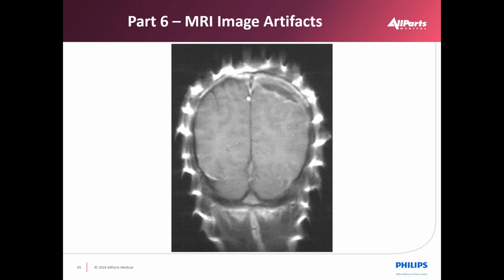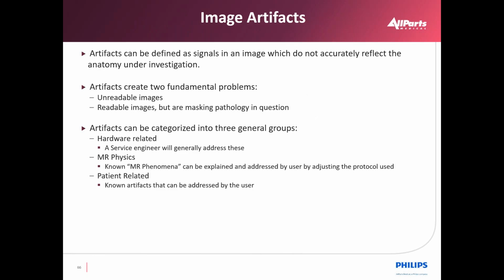Part 6, MRI image artifacts. Artifacts can be defined as signals in an image which do not accurately reflect the anatomy under investigation. Artifacts can create two fundamental problems: unreadable images, or readable images that are masking the pathology in question. Artifacts can be categorized into three general groups. Hardware related: a service engineer will generally address these. MR physics: known MR phenomena can be explained and addressed by the user by adjusting the protocol used. Patient related: known artifacts that can be addressed by the user.